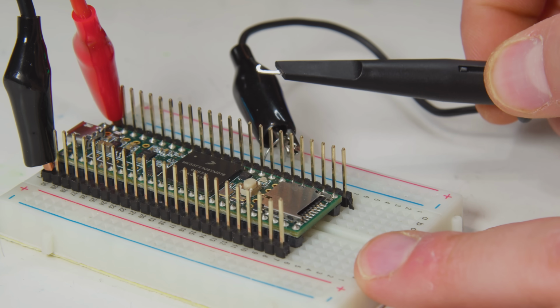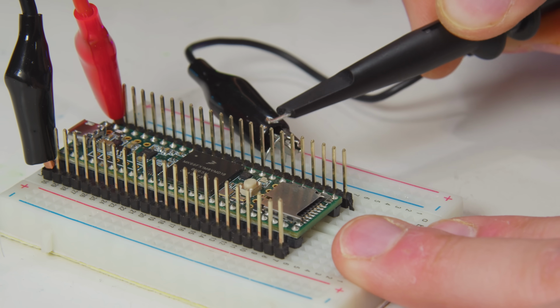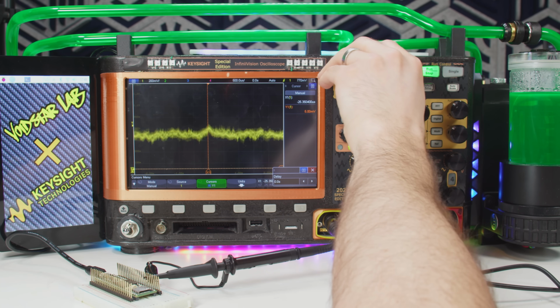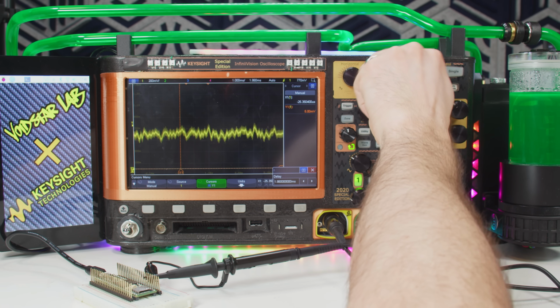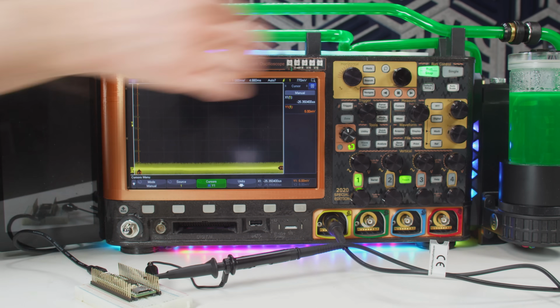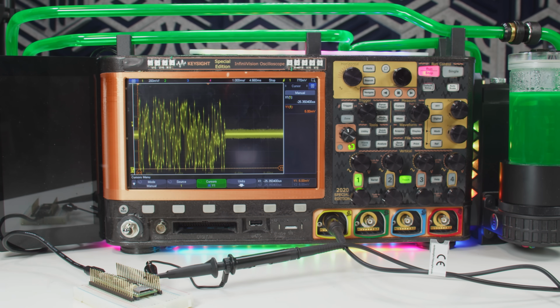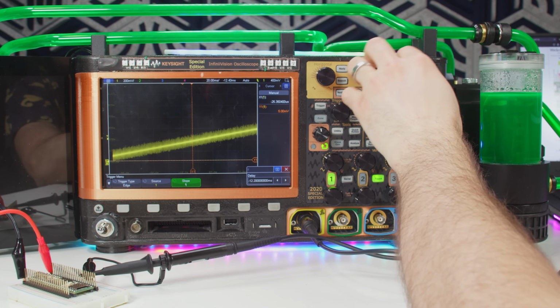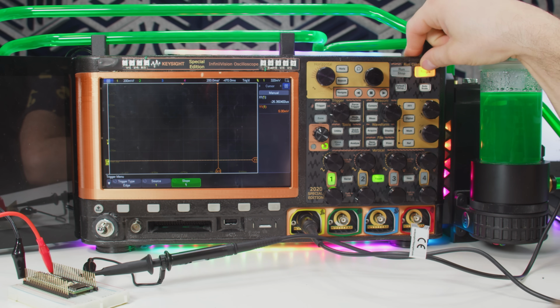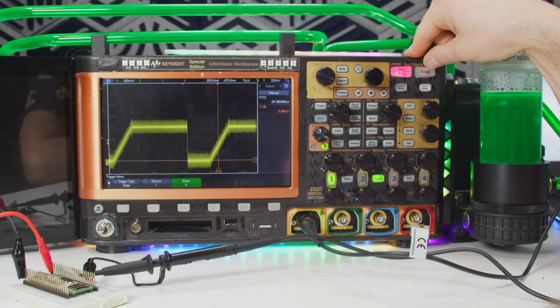Don't lose track of the real world action the curve represents. If you're trying to see what happens when you switch on a gizmo, you want the phase shifted all the way back because, of course, nothing happens when it's off. But if you're diagnosing a brownout, you might want the reverse. You might want to see only what happened leading up to the trigger because you know what happens afterwards.